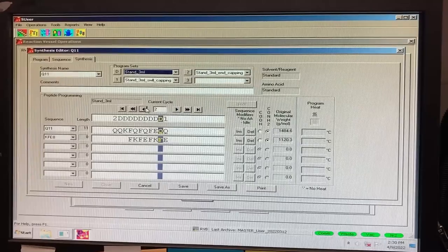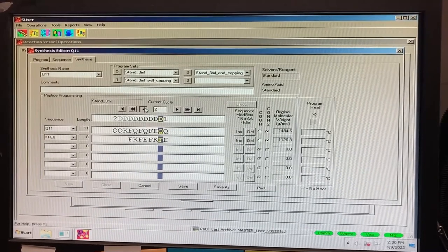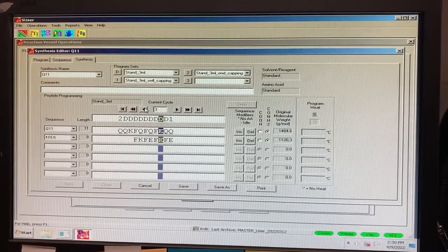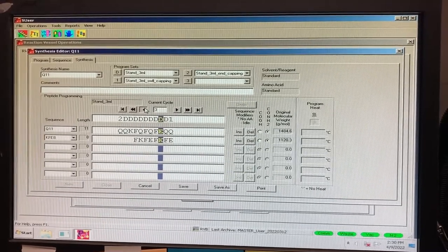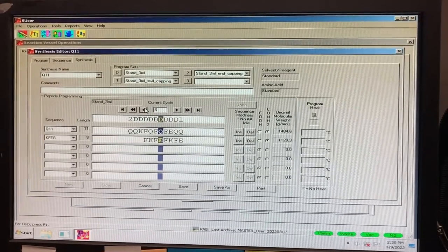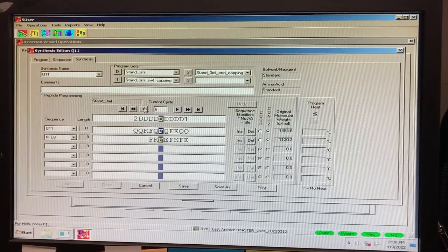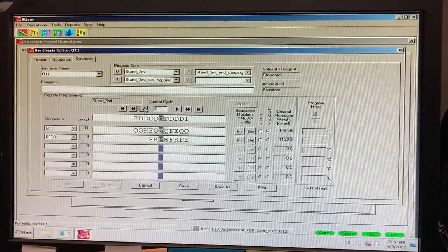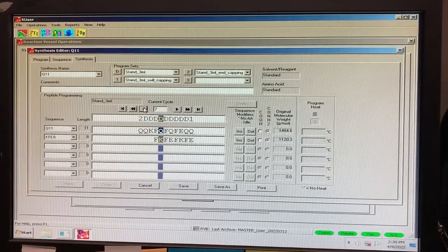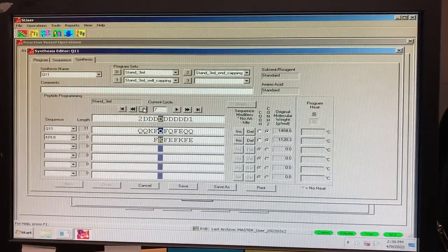If you are running multiple sequences and they are different lengths, you will need to utilize idle cycles. By inputting an idle cycle into a sequence, you are telling the instrument not to perform the selected program on that specific reaction vessel.